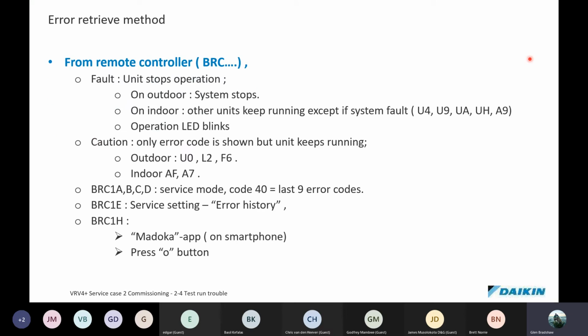All right, so from a remote controller, the fault: the unit stops operation. On the outdoor unit, the system stops. In indoor, other units keep running except if the system is U4, U9, UA, UH, or A9. An operation LED on the remote blinks. We're talking about the operation LED on the remote, not that little green happy light that's flashing on the PC board. Caution, only the error code is shown, but the unit keeps running. These are for outdoor U0, L2, F6, and the indoor unit AF and A7.